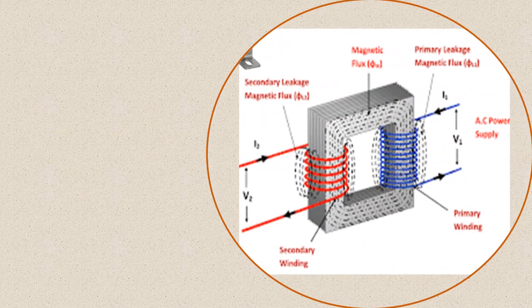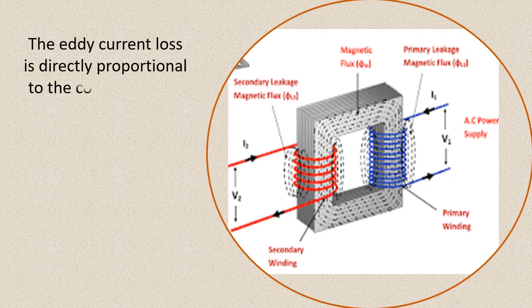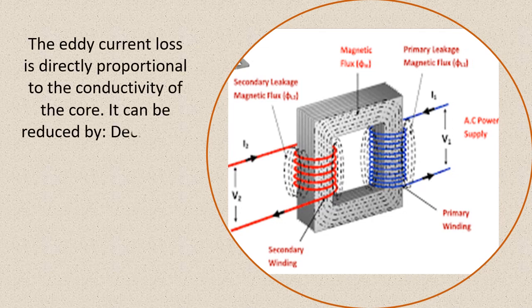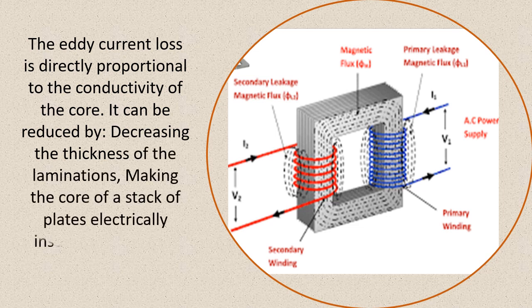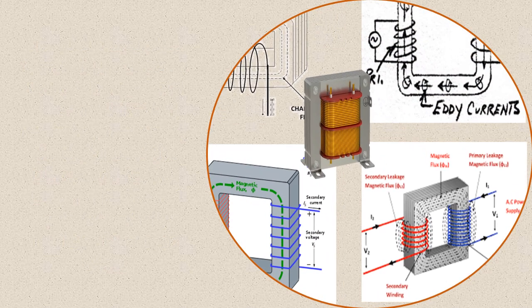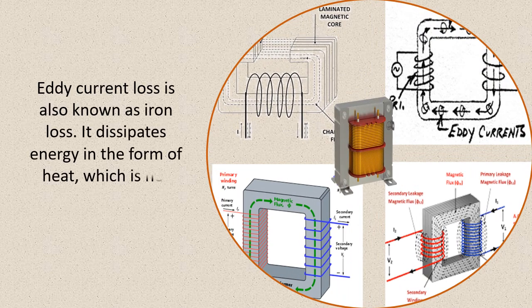The eddy current loss is directly proportional to the conductivity of the core. It can be reduced by decreasing the thickness of the laminations, making the core a stack of plates electrically insulated from each other. Eddy current loss is also known as iron loss. It dissipates energy in the form of heat, which is not utilized for any useful work.